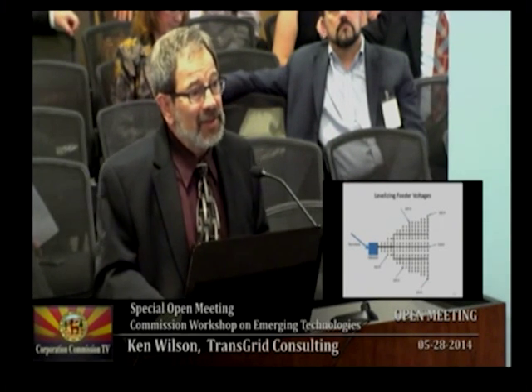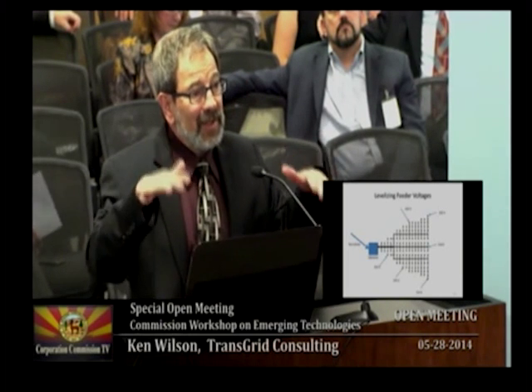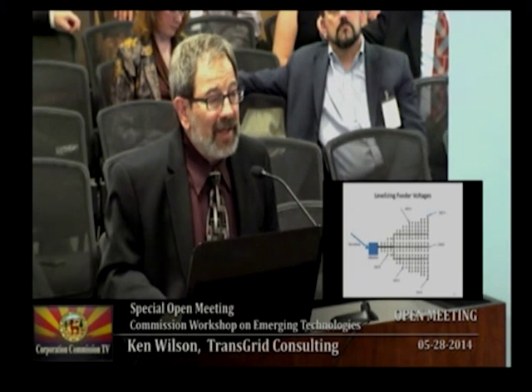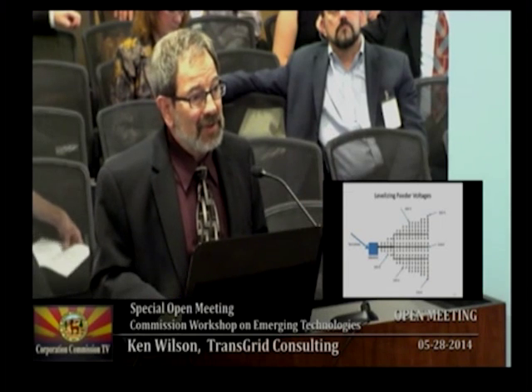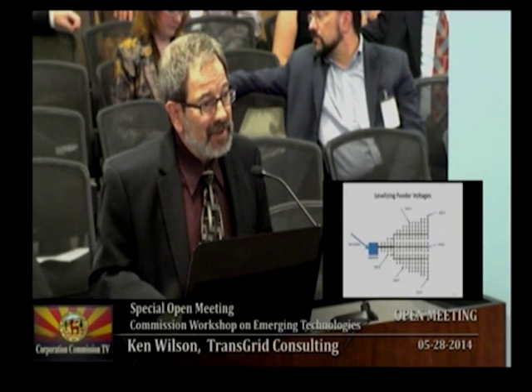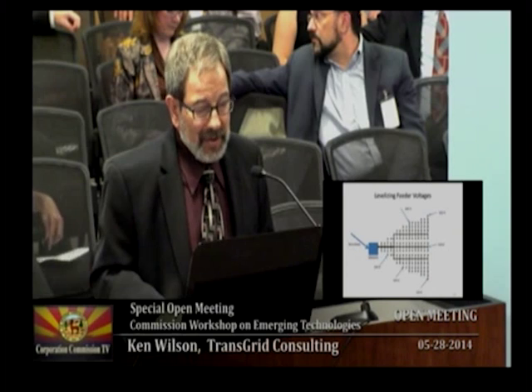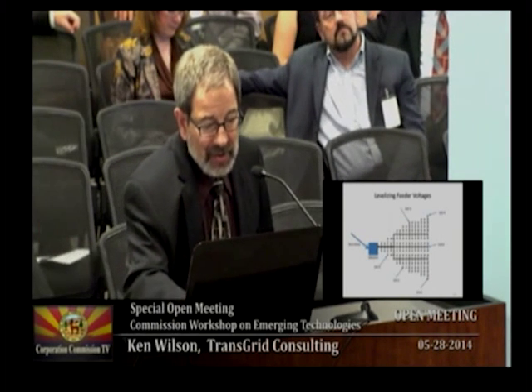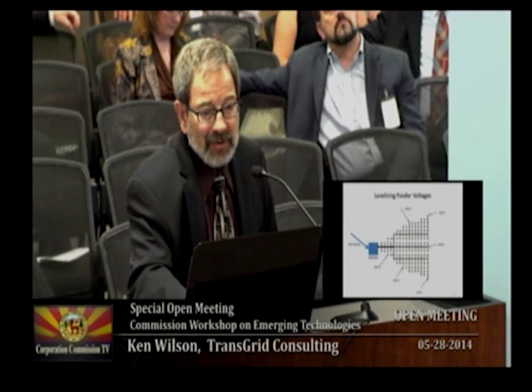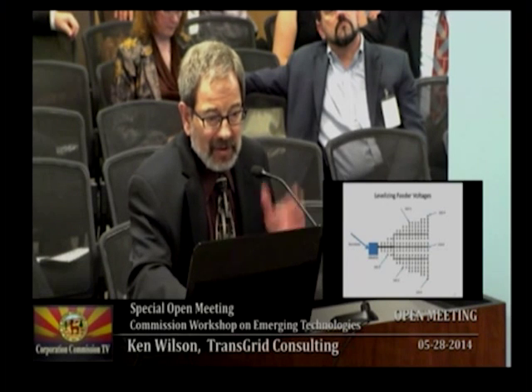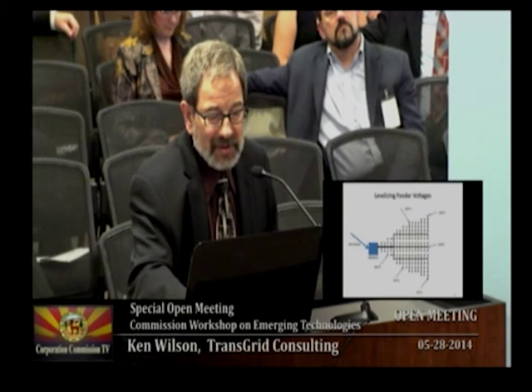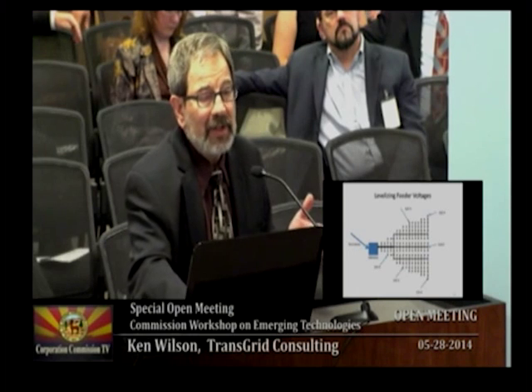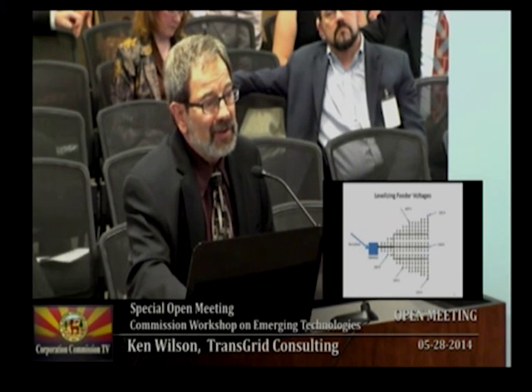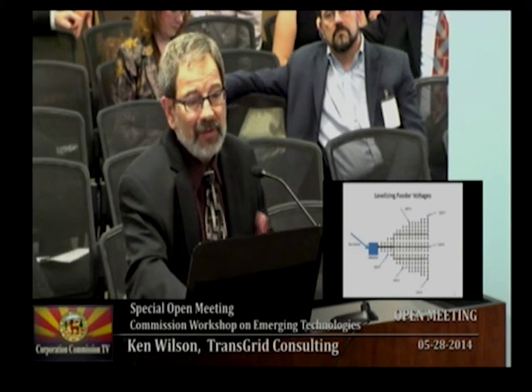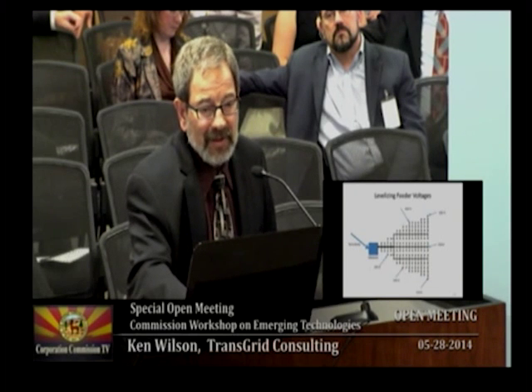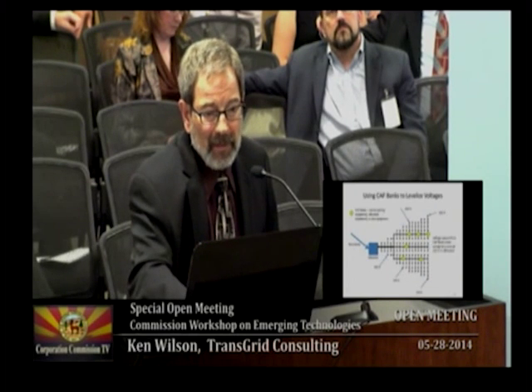And so the utility has to be very careful to maintain the voltages in an adequate range so we don't start burning out people's air conditioners or refrigerators. So the utility is very careful in what they do with the changes in voltage at the substation, because they don't really know what those voltages are on a continuous basis. They don't have the metering today out in the grid to watch that.